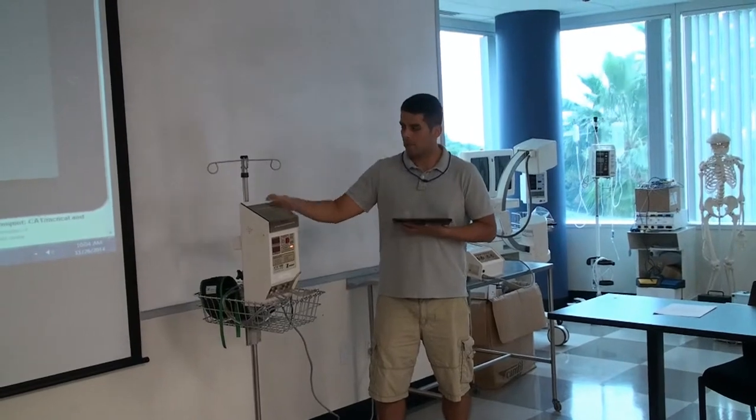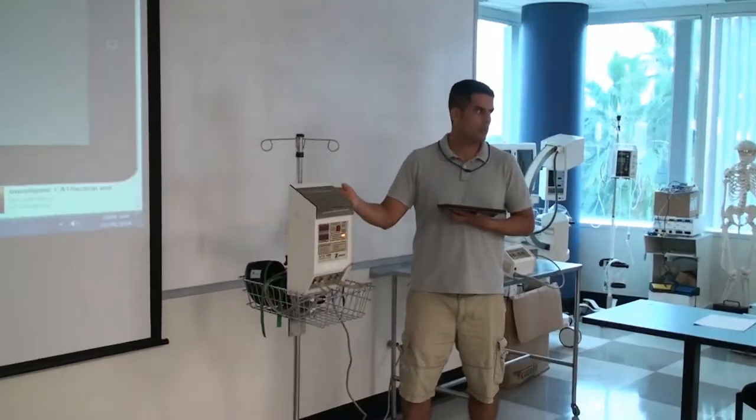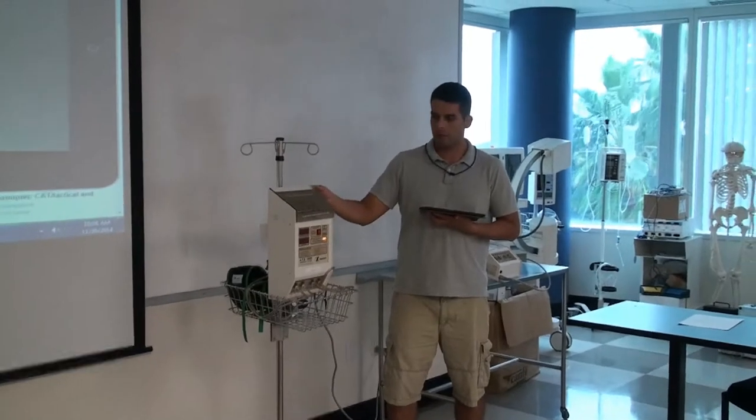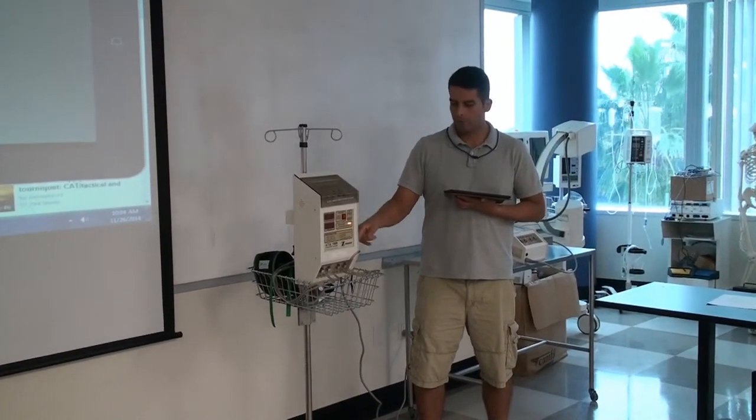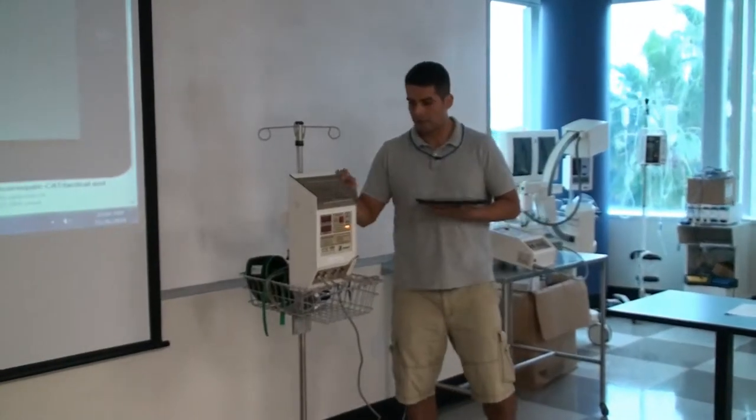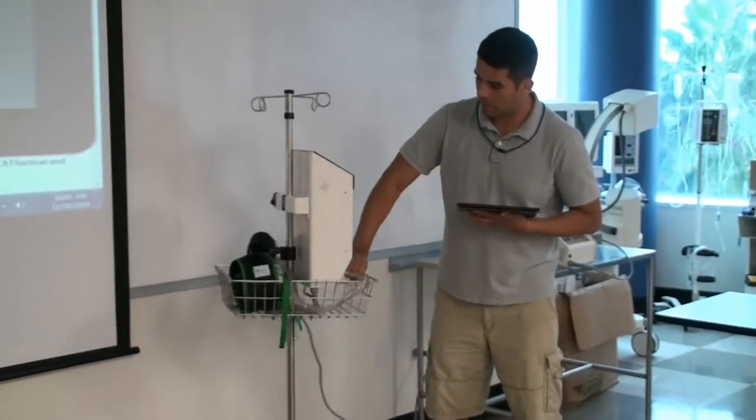Physical inspection. Every six months, the manufacturer recommends a physical inspection of the exterior and interior. Pretty much no rust, clean, no dust.